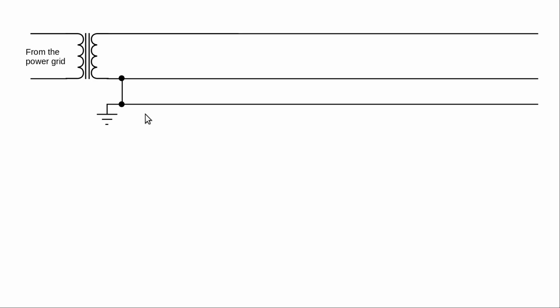And now there's a difference between those two, because this one will be held at earth potential, and this is why we give those wires separate names. This one is live, this one is neutral, and this one is protective earth. And now you may ask yourself, why do we even have a separate neutral and protective earth wire? Because as we can see here, they are at the same potential, and having two wires would just be a waste of copper.